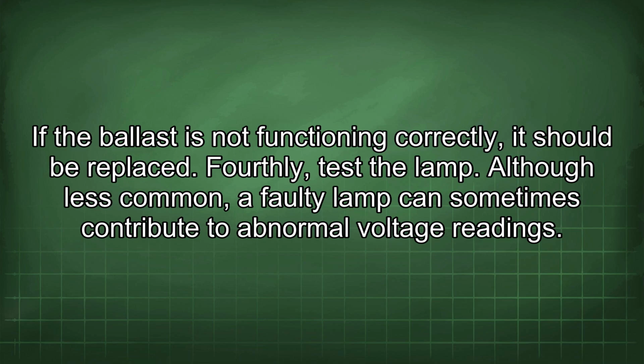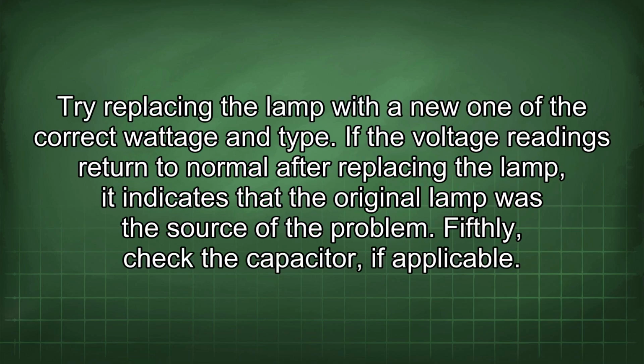Fourthly, test the lamp. Although less common, a faulty lamp can sometimes contribute to abnormal voltage readings. Try replacing the lamp with a new one of the correct wattage and type. If the voltage readings return to normal after replacing the lamp, it indicates that the original lamp was the source of the problem. Fifthly, check the capacitor if applicable.